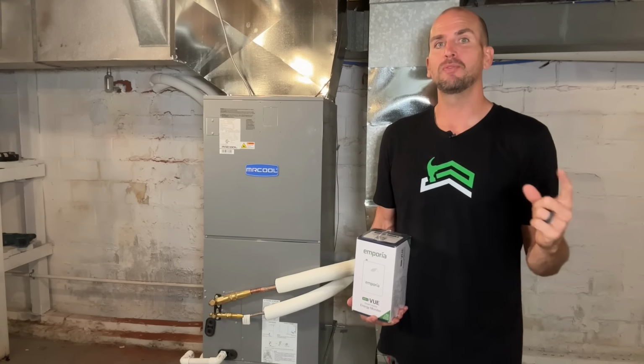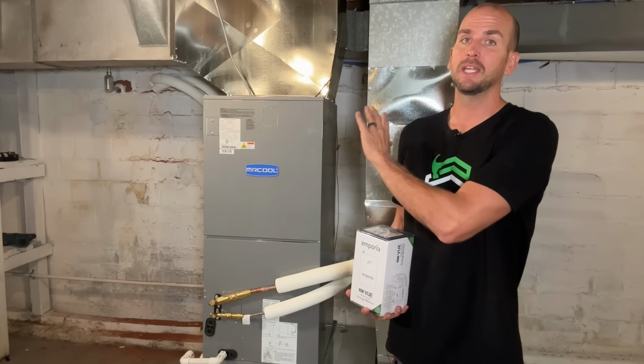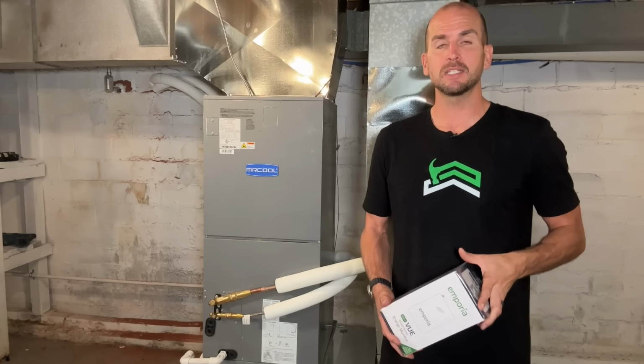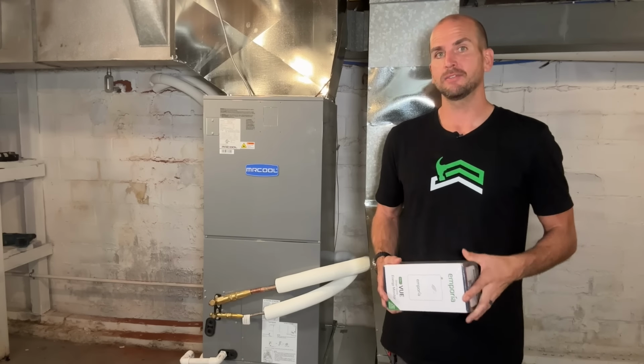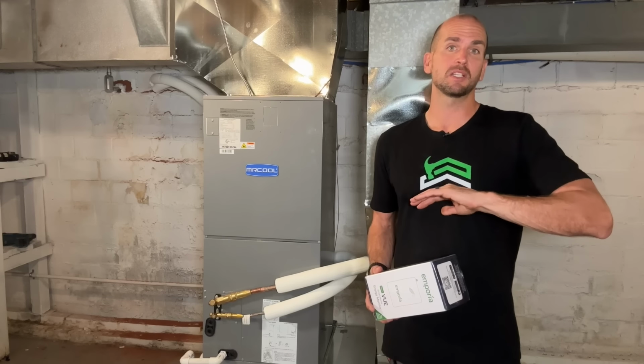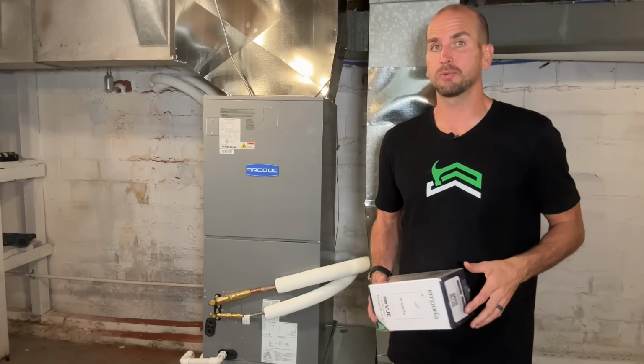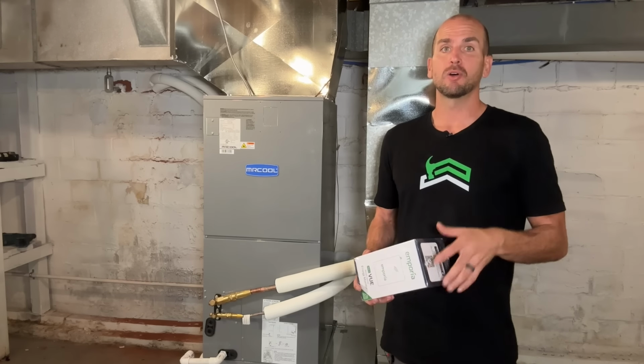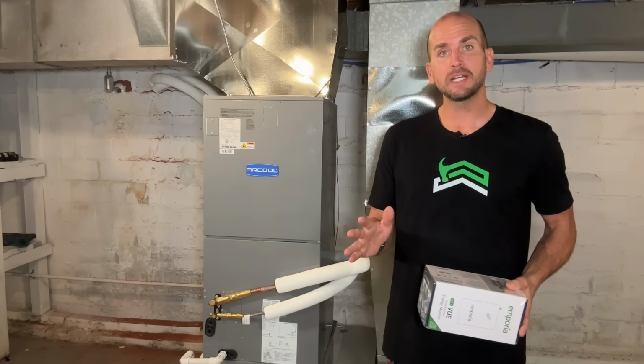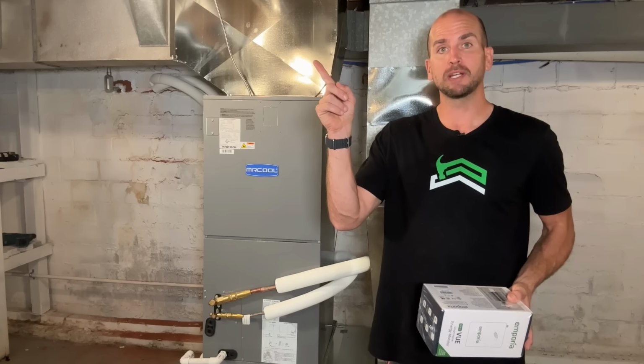It also will validate, without any heating coils or any additional heating capacity, whether this heat pump is effective at heating this property when the ambient conditions are super cold. And that is exactly what the HyperHeat is supposed to do. So I'll validate that and include that in a video with my findings, which you'll find right here.